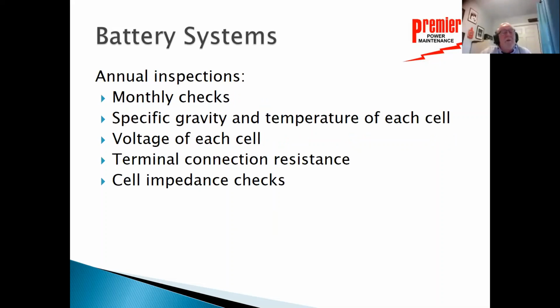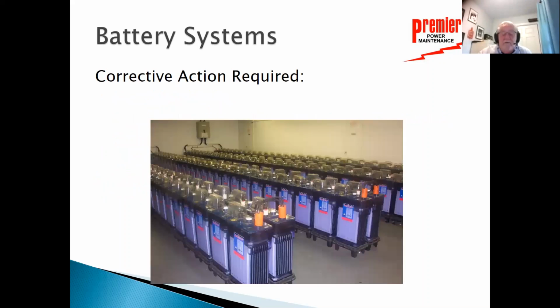Again, it's still the most important part of your system. And on annual tests, do all of those monthly and quarterly checks, and do the specific gravity of each specific cell, the voltage on each cell. Check the terminal connection resistance. They can still look good, but we can have some resistance increases there that are really a problem. And one of the easiest things for us to do is to have a device that will check the impedance of each cell. That's a true indicator of how the system is going.